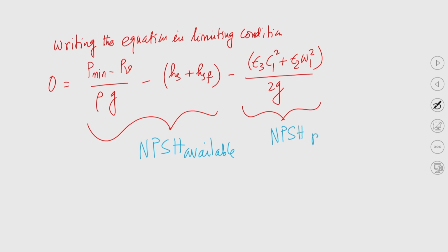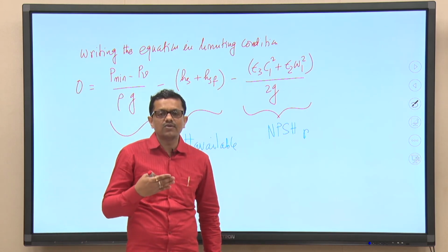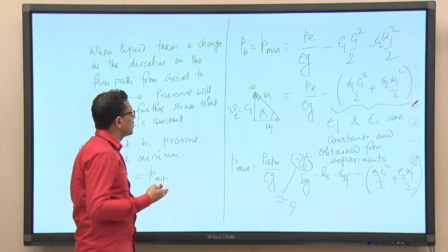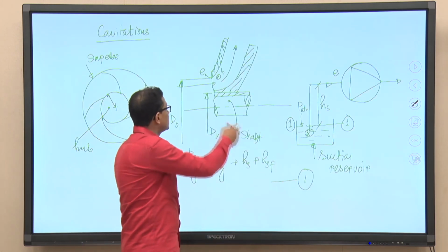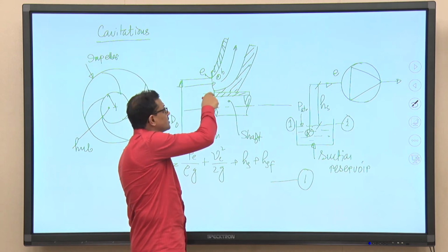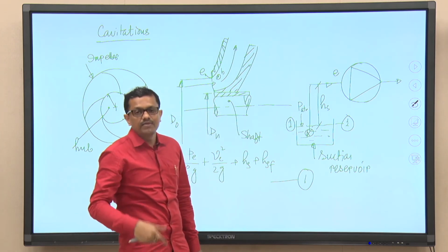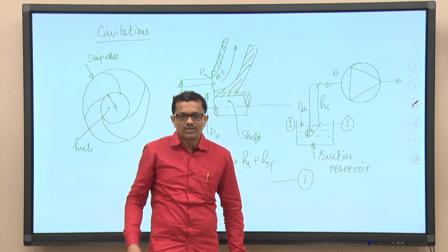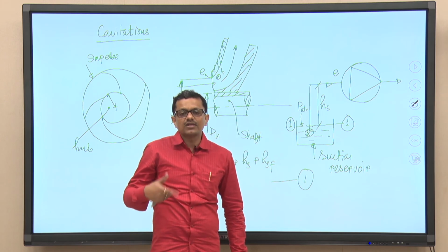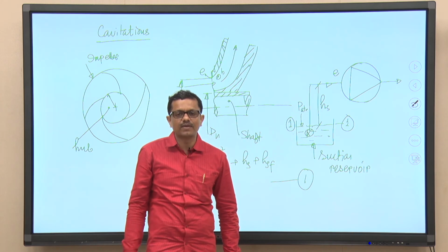When a pump is designed, a pump designer should take into account what the NPSH required will be. If we go to the previous slide wherein I have drawn the schematic depiction, when liquid changes direction from purely axial to radial, and also due to the constricted flow passage, velocity will increase and the liquid will accelerate; that we cannot prevent. At the cost of that increment in fluid velocity, pressure will fall, and if pressure falls below the vapor pressure, cavitation will occur.